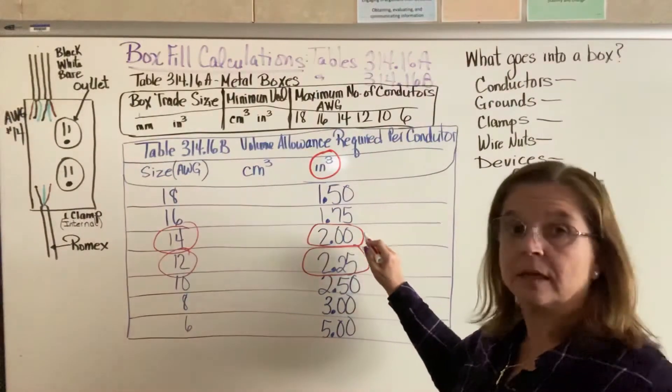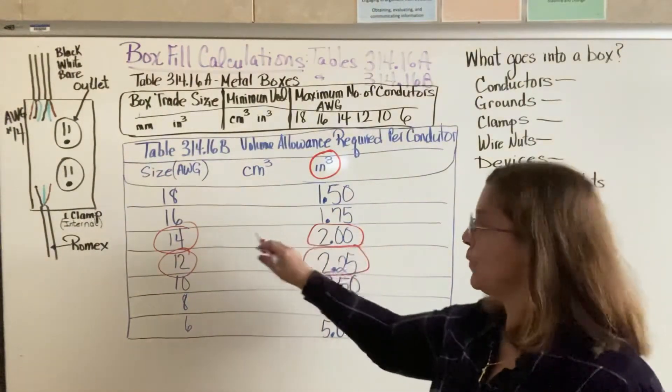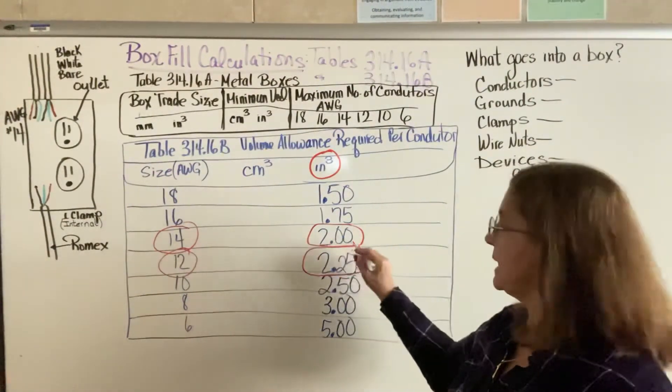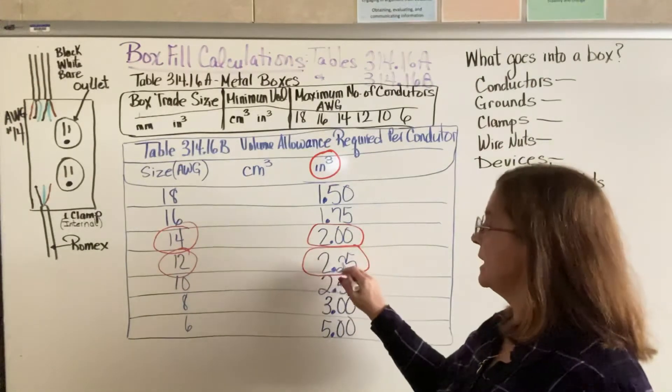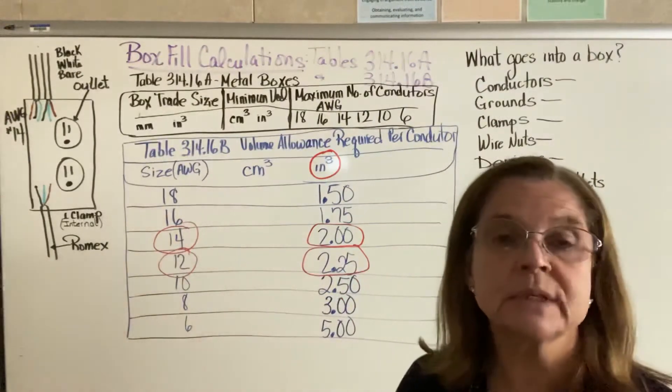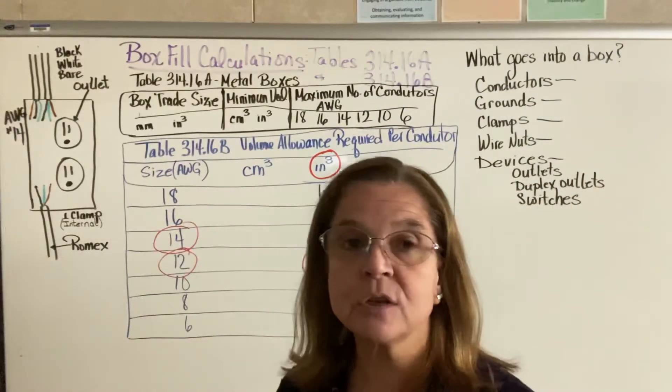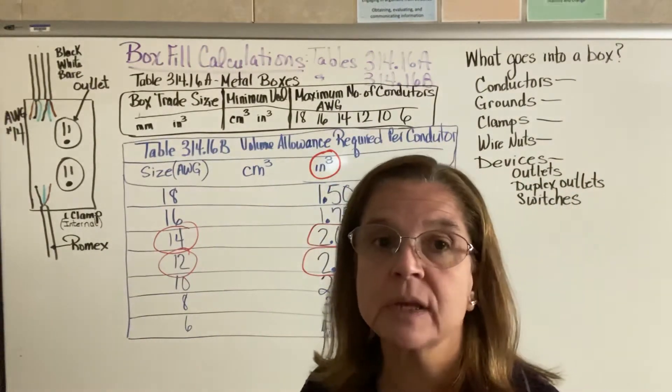Every conductor that is size 14 will take up 2 cubic inches of space. Every conductor that is size 12 will take up 2.25 cubic inches of space.